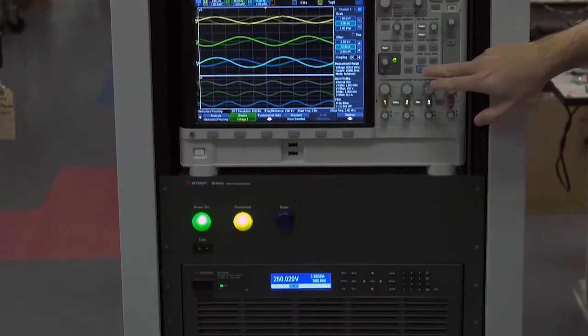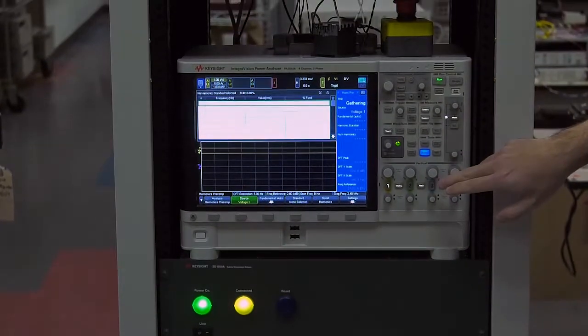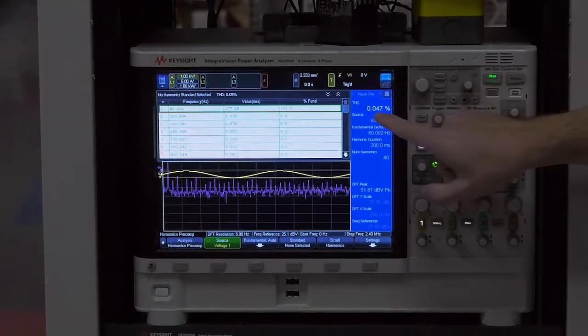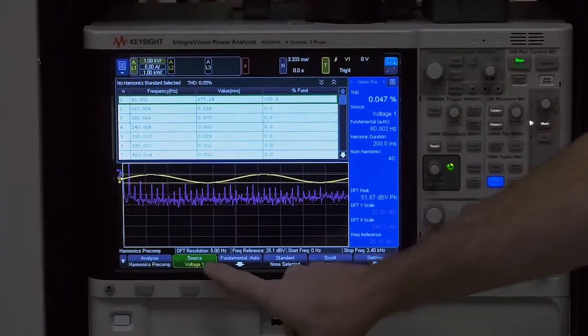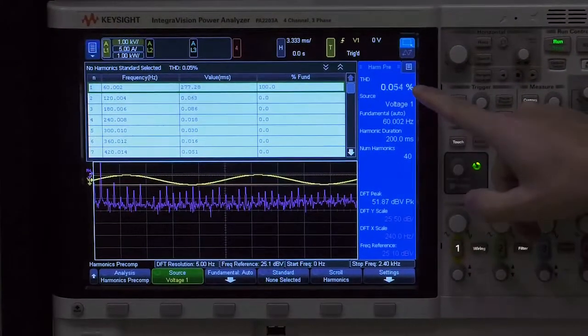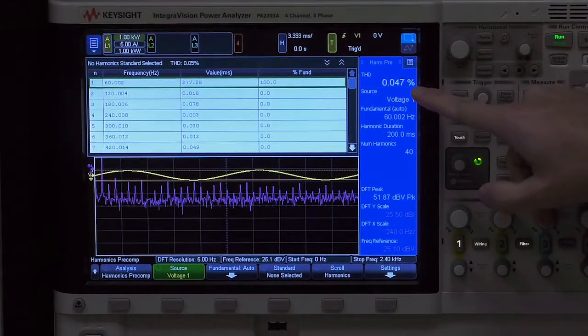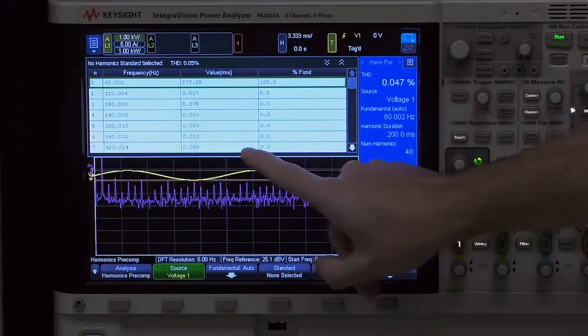We'll go back up to the power analyzer. We'll hit the analyze button. You can see the total harmonic distortion on one of the phases of voltage is extremely low at 0.05 percent. You can also see some of the harmonics.